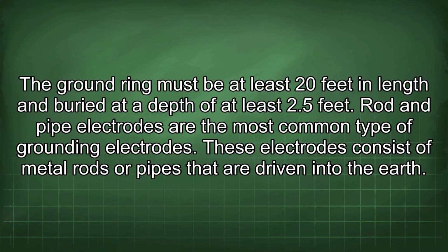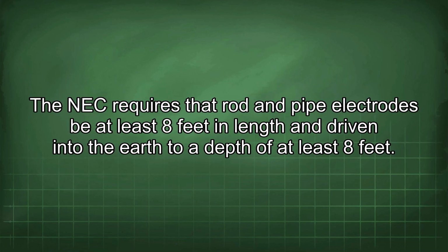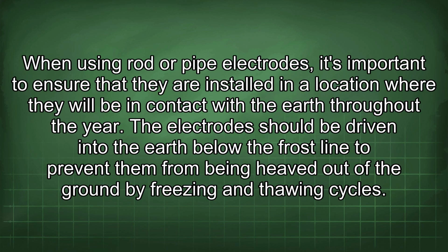These electrodes consist of metal rods or pipes that are driven into the earth. The NEC requires that rod and pipe electrodes be at least 8 feet in length and driven into the earth to a depth of at least 8 feet. When using rod or pipe electrodes, it's important to ensure that they are installed in a location where they will be in contact with the earth throughout the year. The electrodes should be driven into the earth below the frost line to prevent them from being heaved out of the ground by freezing and thawing cycles.